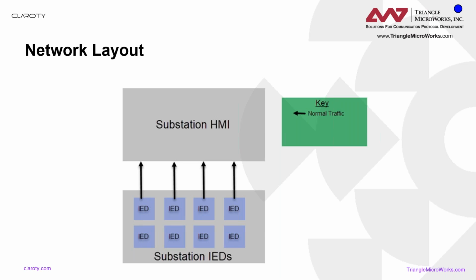So this is kind of a normal network layout. In our simulated network, we'll have our substation IEDs that will be monitoring information and sending it up via 61850 reporting to the substation HMI. There will also be GOOSE published among the IEDs themselves. We've also added a semi-periodic control from the substation HMI down to a select few of the IEDs. While it'll be more frequent than you'd expect in a normal system, it will add a little more detail to the simulation for a more well-rounded system for CTD to monitor.